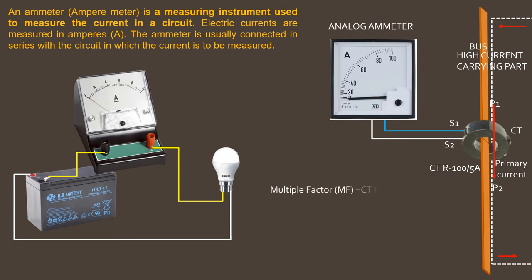Multiplication factor is equal to CT ratio divided by meter CT ratio. Here, the multiplication factor is one. The reading of the ammeter is to be multiplied by multiplication factor to get actual reading.